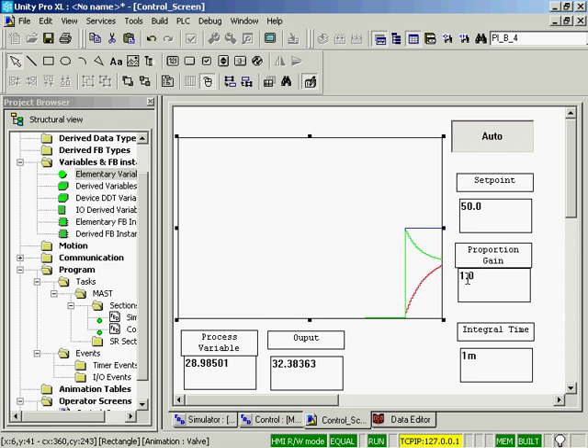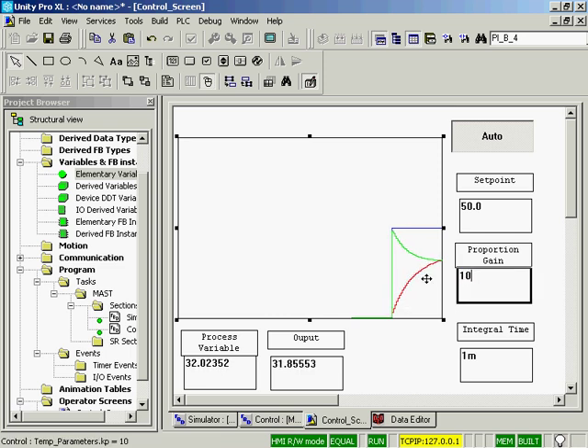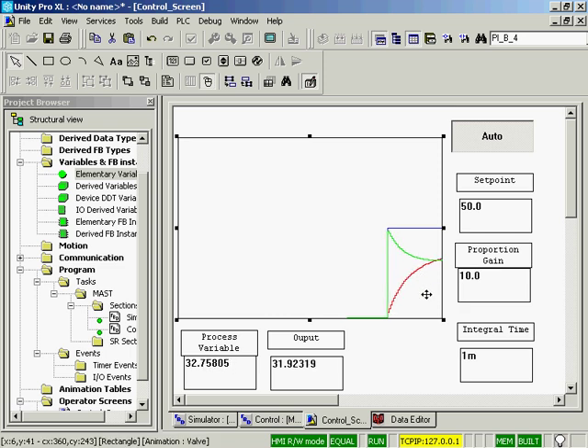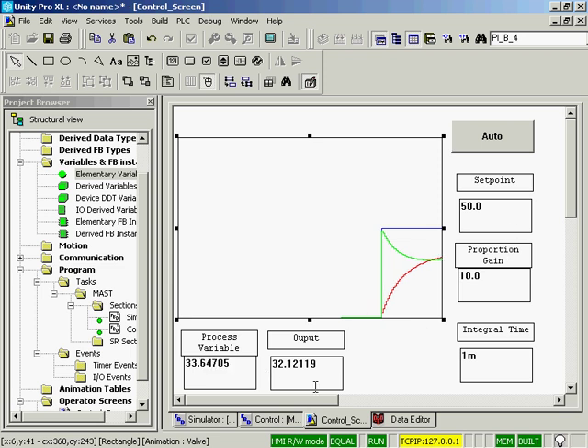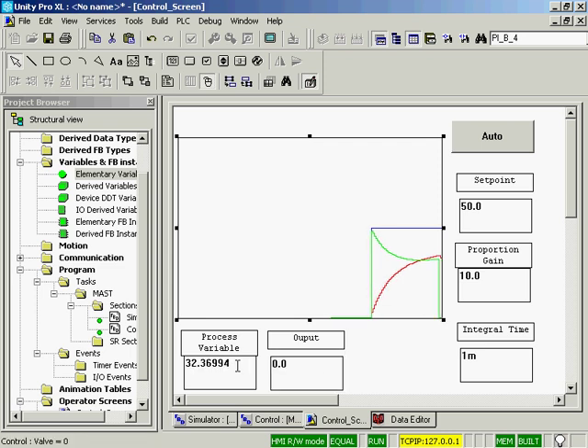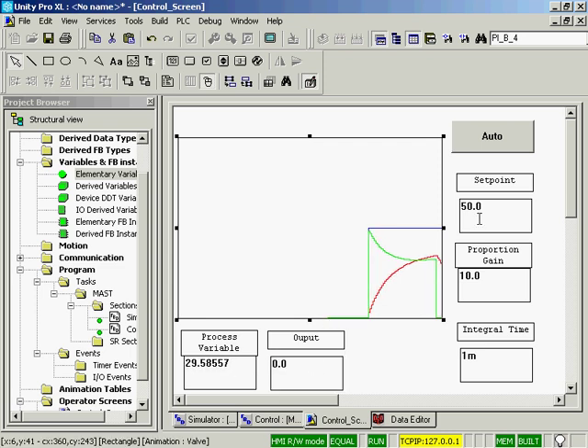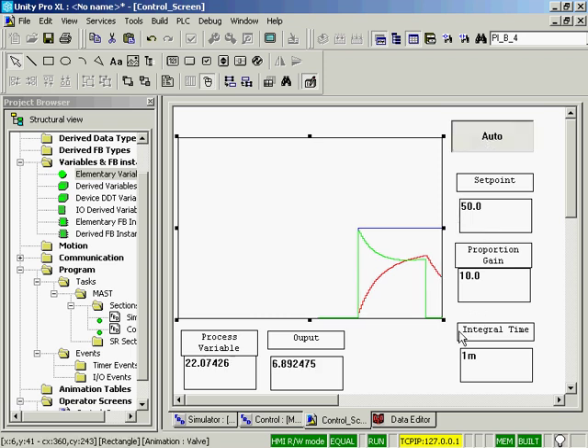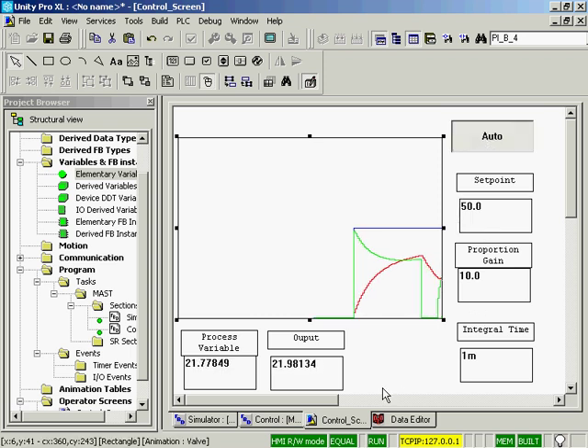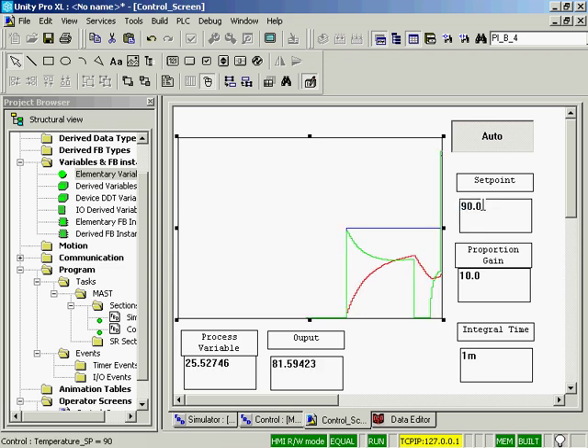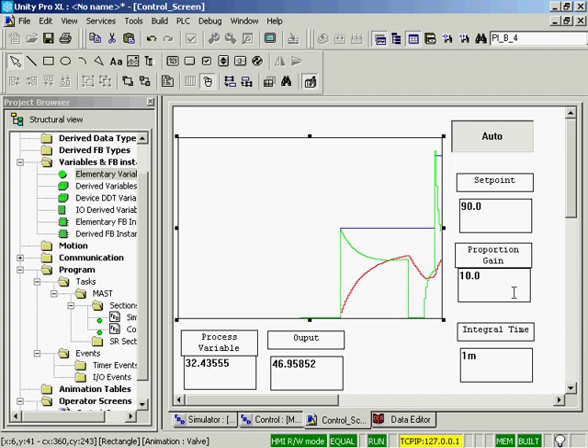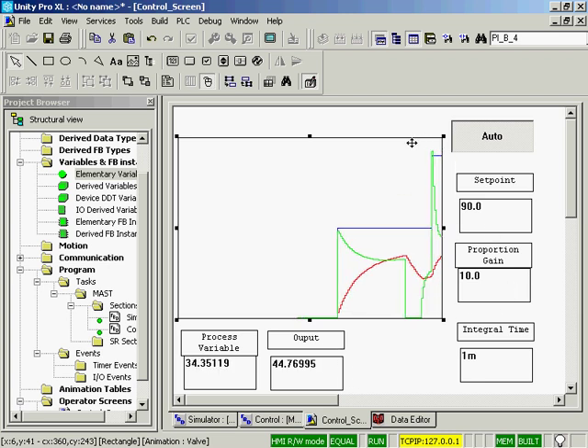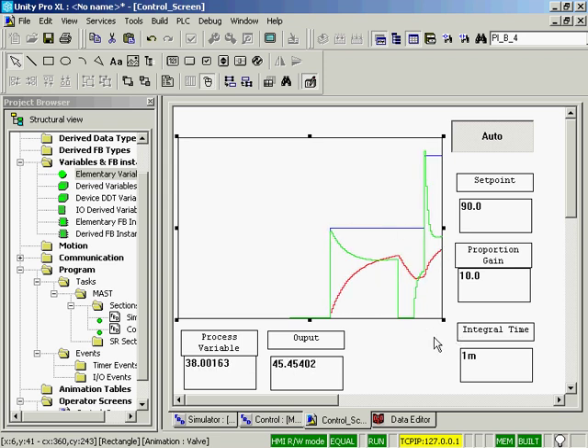We can see a nice even ramp as we're getting close. The proportional gain is telling us how fast we're going to get close. So I'm going to change the proportional gain to 10. I will take it out of the loop. I will set the setpoint and set the output back to zero. We'll see the process variable go down. We'll change the setpoint to 90 degrees and I'll put us back in auto. You'll see how the output with the proportional gain screamed right up there and is now coming down.